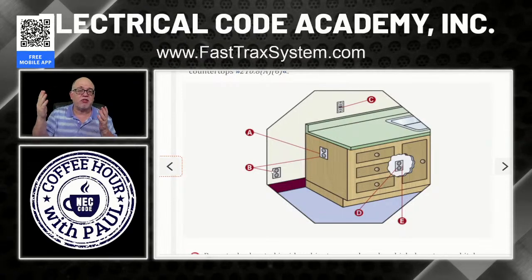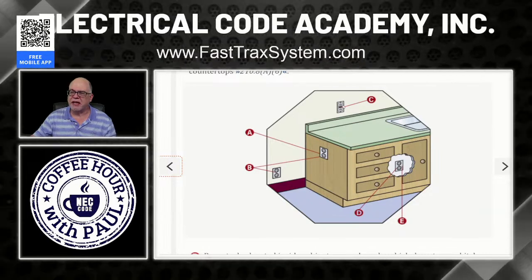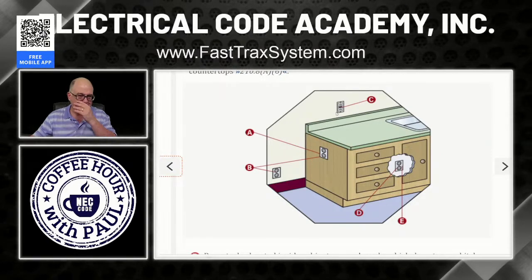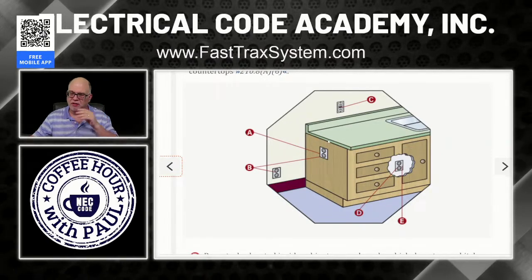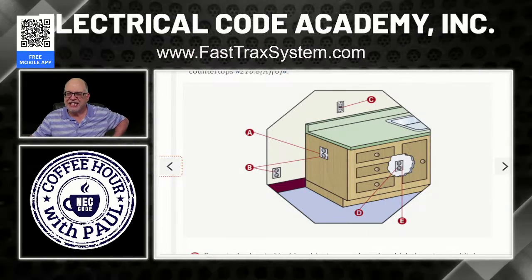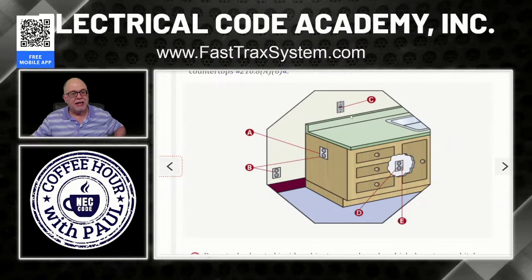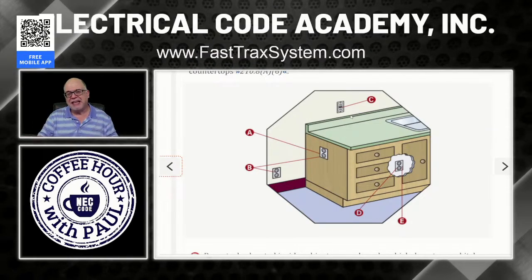Now they are probably going to be on the same small appliance branch circuit, but this is a receptacle placement rule, okay? So it's just something to keep in mind. For example, maybe this receptacle is serving the countertop, right? And this overhang is not more than 6 inches. Well, if I have a doorway right here and this is wall space and this receptacle is, say, within 6 feet of this doorway, it could not meet this wall space requirement because it's here to serve the countertop requirement. You can't do double duty. And that's what it's trying to say.